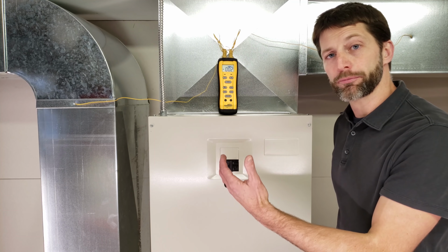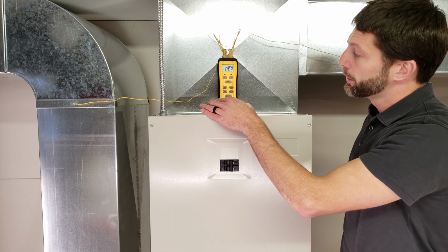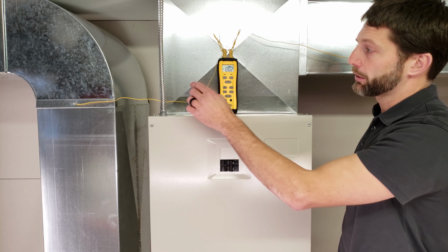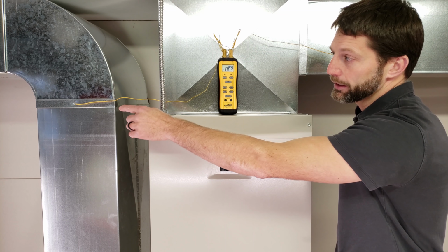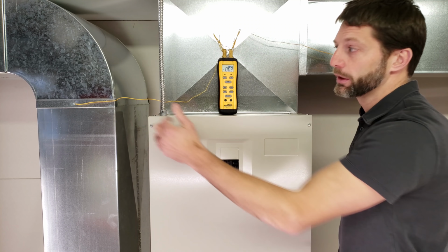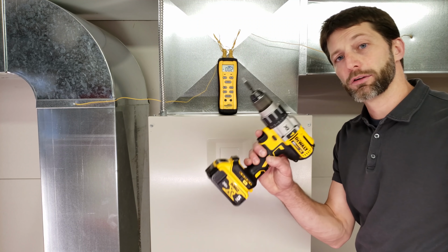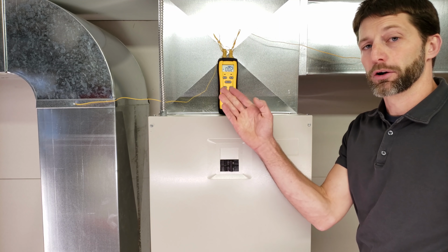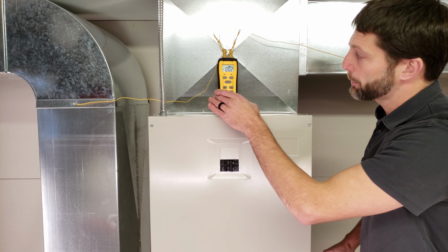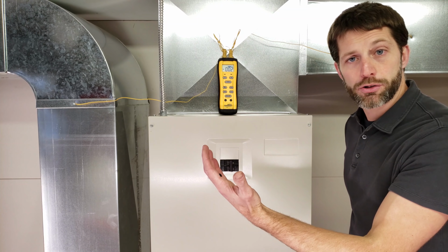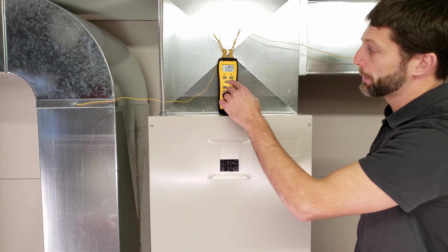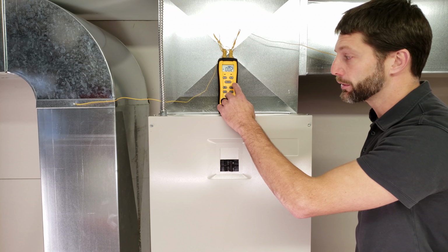So the Delta T is the actual change in temperature between the return duct and the supply duct, and in this case we're using a dual temperature meter and we're sticking our small K-type bead temp sensors into the holes, and what we did is we just drilled 1/4-inch zip screw holes into the ducts, and that's how we're taking our reading. So on this temperature reader we're actually able to take a differential reading between the return and the supply by selecting the T1 minus T2.